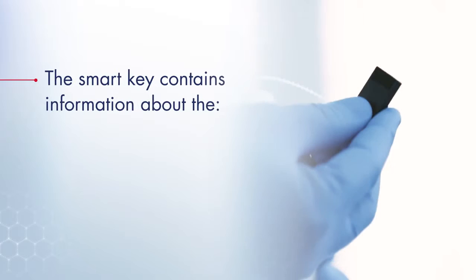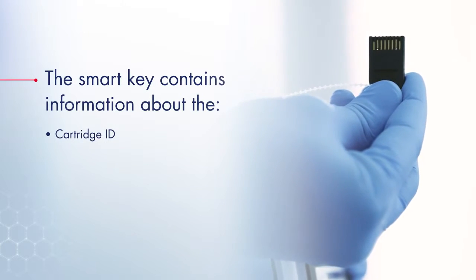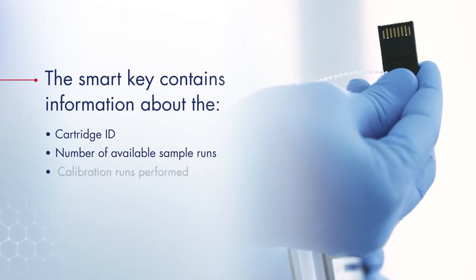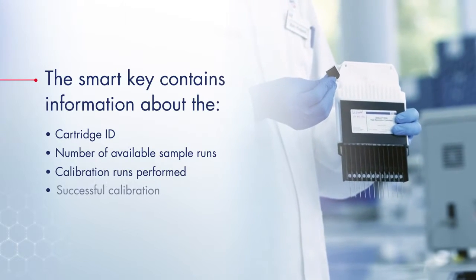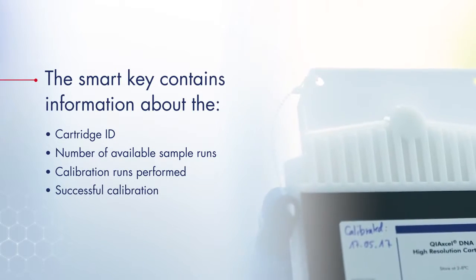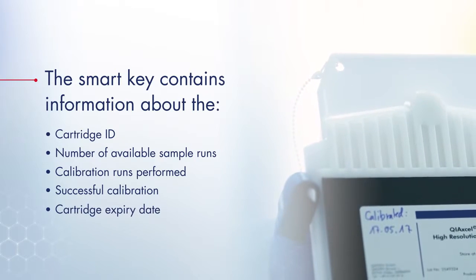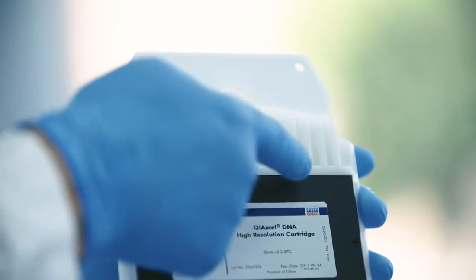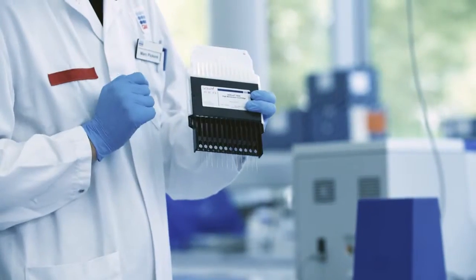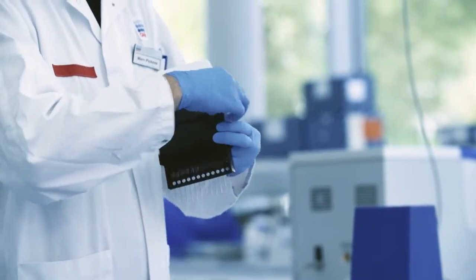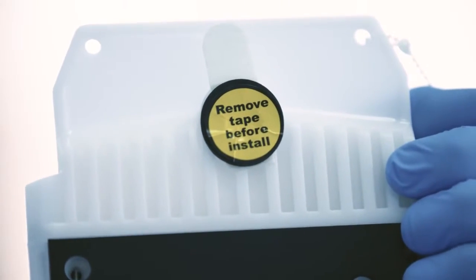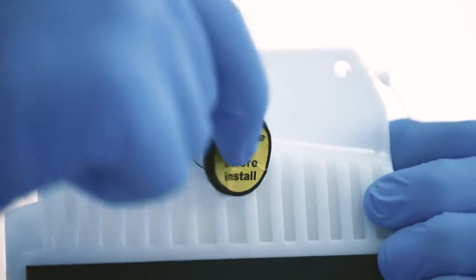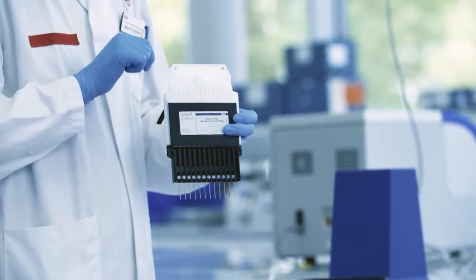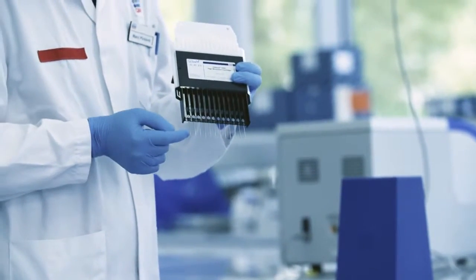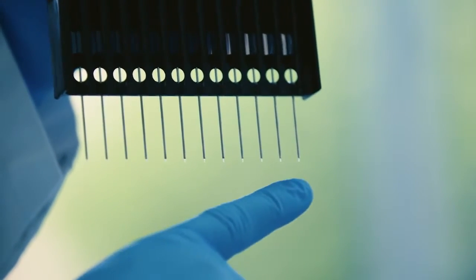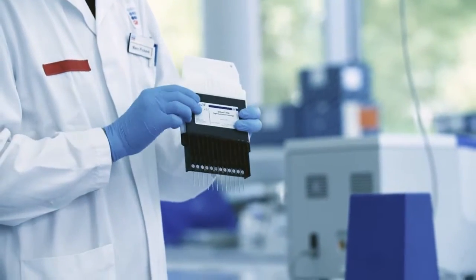The smart key contains information about the cartridge ID, the number of available sample runs, and calibration runs that have been performed, the successful calibration with the QIAxcel Advanced, and the cartridge expiry date. The gel reservoir of the cartridge contains the gel which is used for the run. The gel is replaced for each new run. Nitrogen pressure is applied via the purge port, enabling the instrument to replace the used gel from the previous run with fresh gel for the next run. Analytes are loaded into the gel capillaries and separated by size under the application of an electric field.